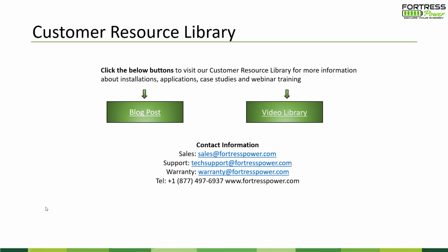The 2-unit limit will be expanded with future product generations. But for now, for large commercial projects with a tremendously large battery bank, battery-empty or battery-voltage-high are really your triggerable effects. Residential customers want to see percent state of charge, in which case you'd have to use the eFlex if you want battery storage capability larger than 37 kilowatt hours — although stay tuned for product announcements in the future on that.